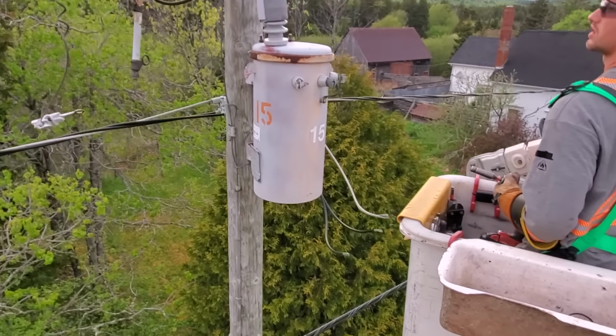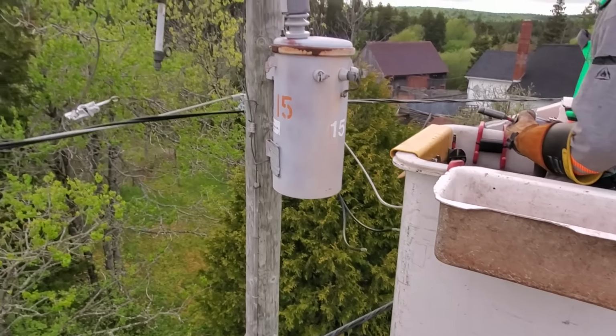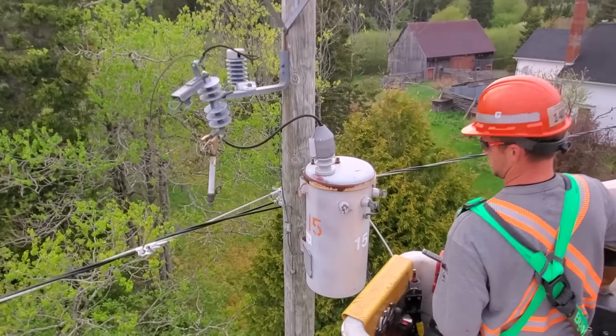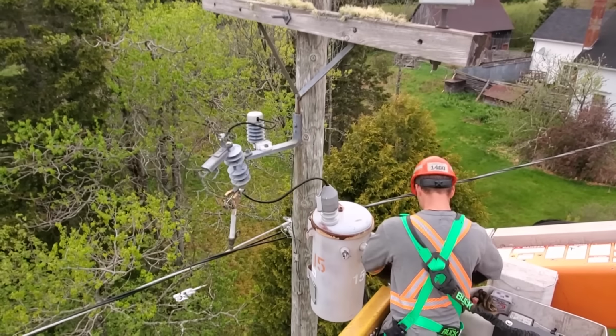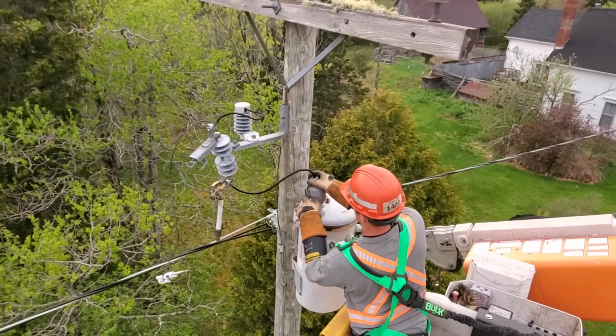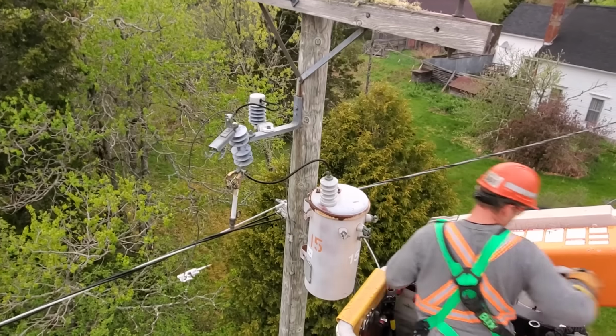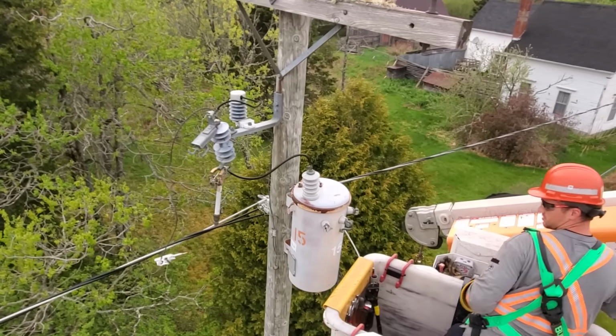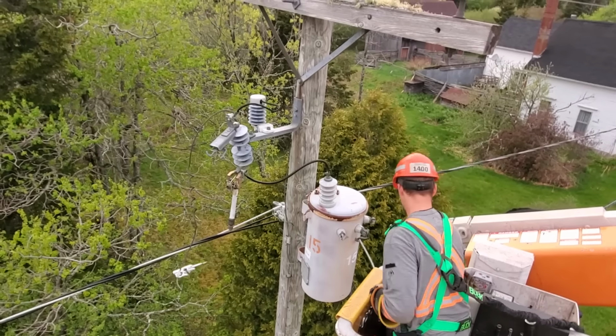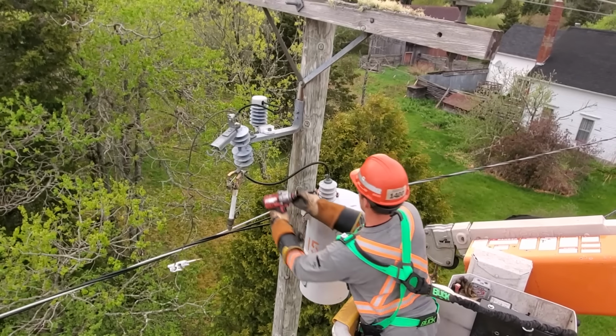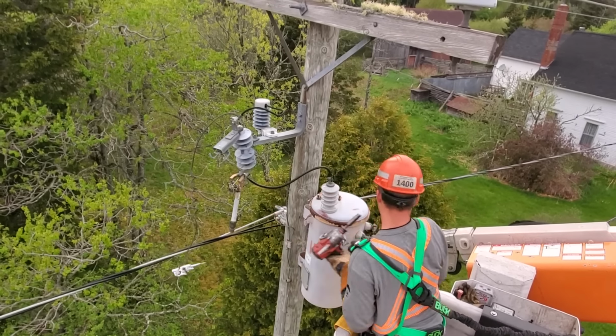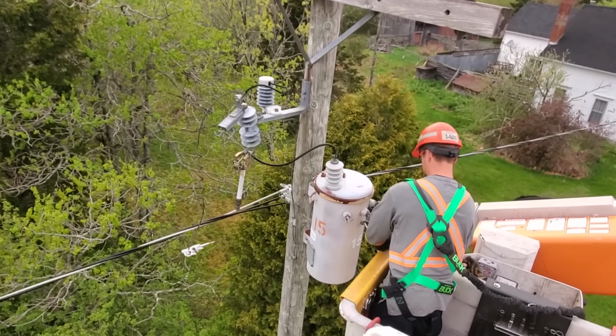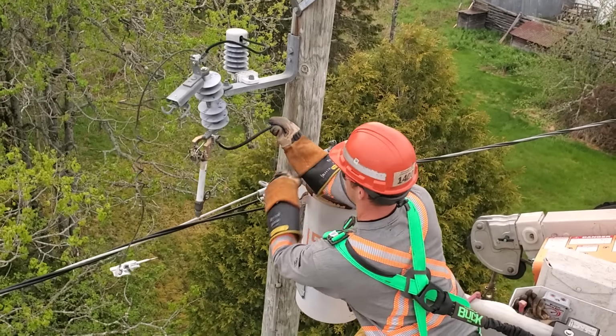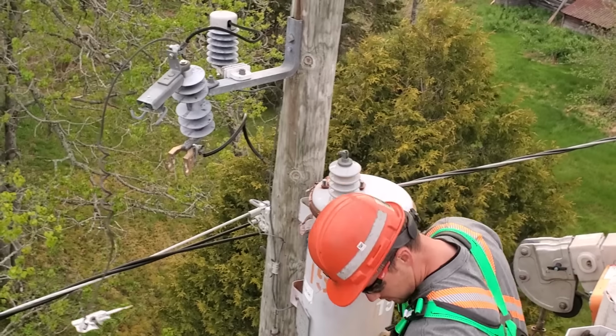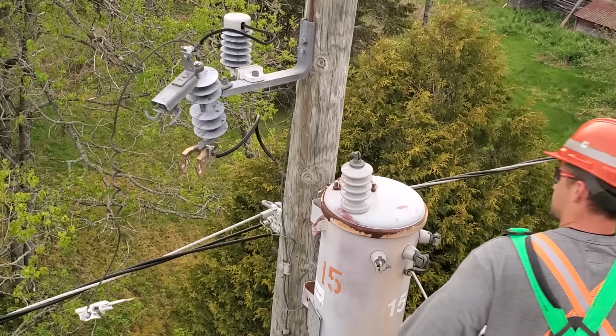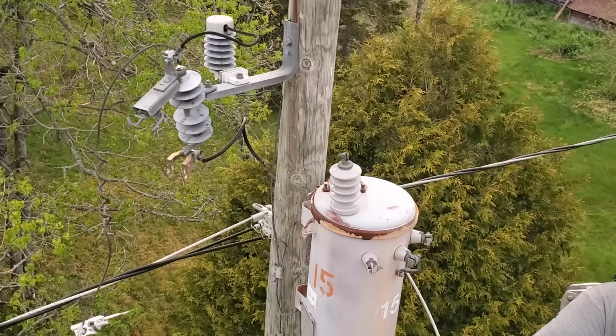Another thing I'll mention, that's aluminum wire. Anytime you do have that style bushing, you want to make sure you use copper wires. The aluminum is just, over time, loosens up. He's going to save that squirrel guard to install on the new transformer. You can see he's using the Milwaukee power tools to remove all the connections. It's very important you don't over torque those connections when reinstalling them, especially on that primary bushing. It's quite easy to snap that off.